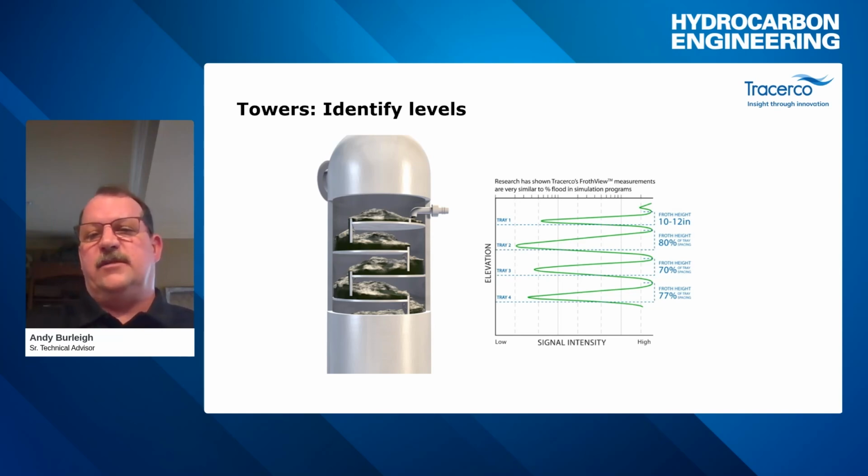Time is one of them, and that's constant. We take the same length count at every spot we check on the vessel. Second is the distance between the source and detector, which pretty much stays consistent from top to bottom, as we lower them right down the edges of the vessel. And then the third thing is the density, and that's actually changing. That's the one thing that's not constant. So what we're getting here is a density profile.